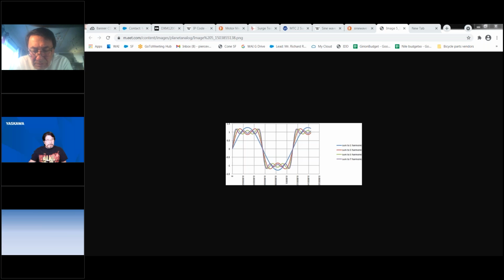The solution. I just want to point out one other thing. I ran across a gentleman a couple of years ago that was out of San Diego, and they started suddenly losing 3 horsepower, 2 and 3 horsepower submersible motors in a residential area. It was driving him nuts. And they were all across the line starters. They were using Franklin controllers. And what we came up with is, I said, check and see if you've got new solar farms nearby, which they did. They had 2 of them installed nearby.